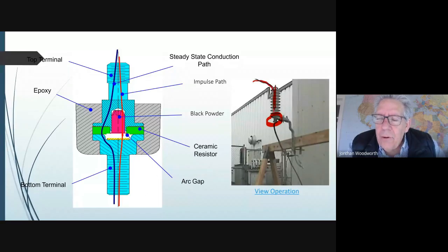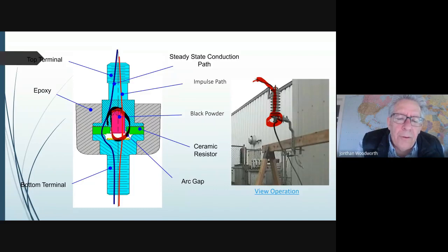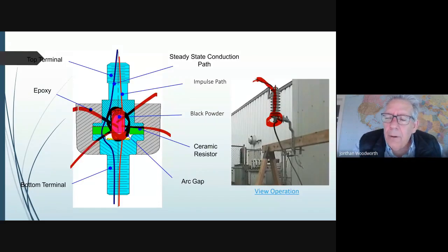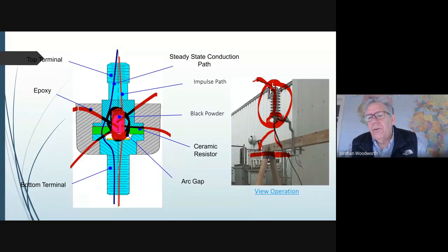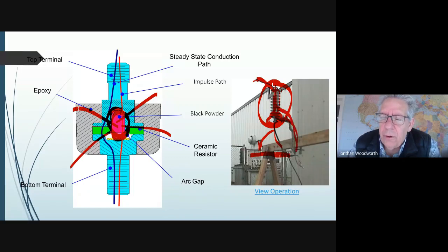During that last event, this disconnector opens and operates. It actually has black powder on the inside, and it blasts the whole thing apart, and the line swings down. So the line comes down, and it disconnects the arrestor from the power system. So this is a way of holding the reliability of a distribution system up. If you didn't have the disconnector, it would stay connected, and you'd have a short to ground, and the whole distribution line would shut down. This way, it automatically disconnects, and then the power can come back on, and it improves the reliability level of a distribution line.